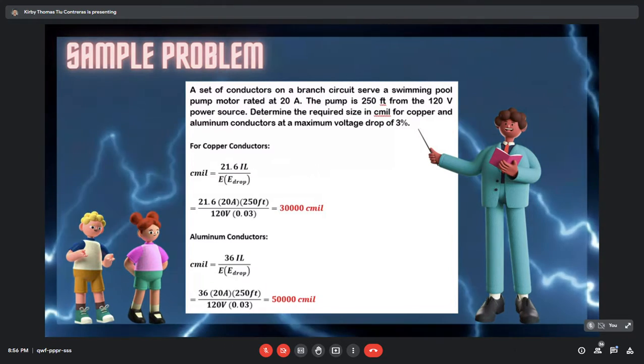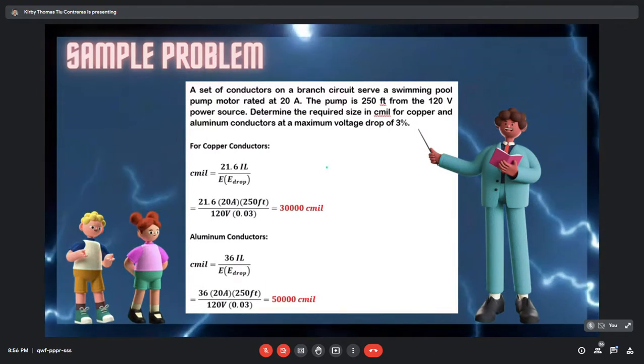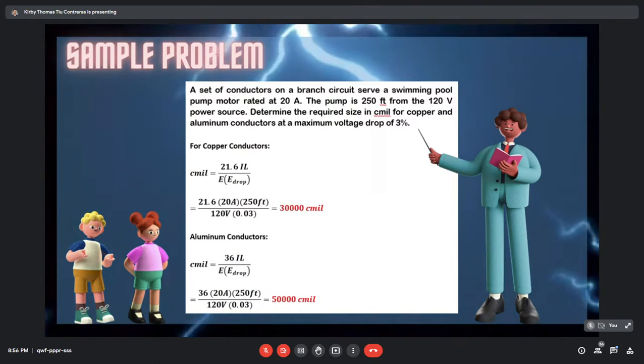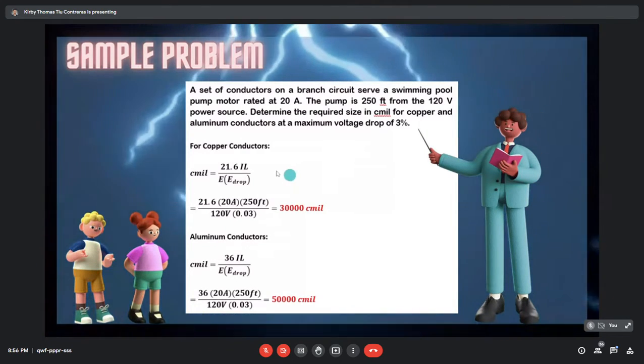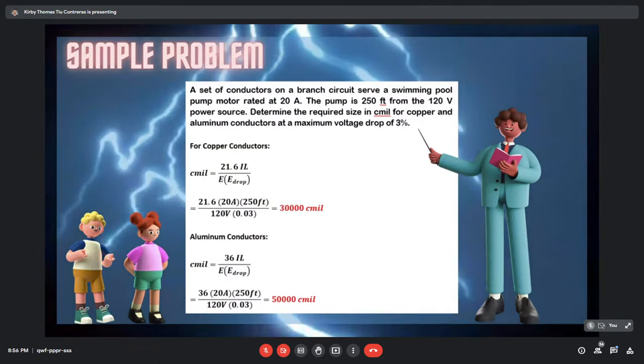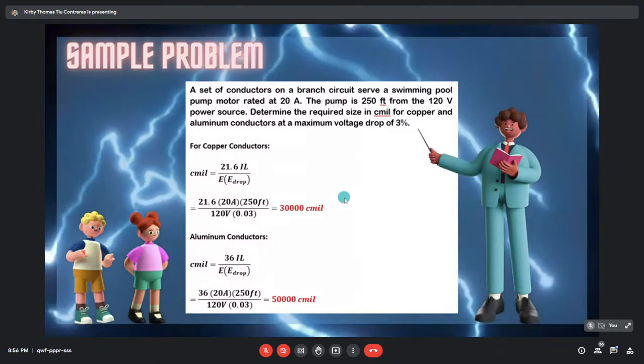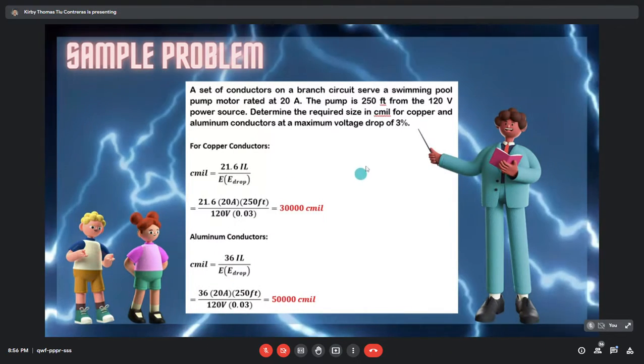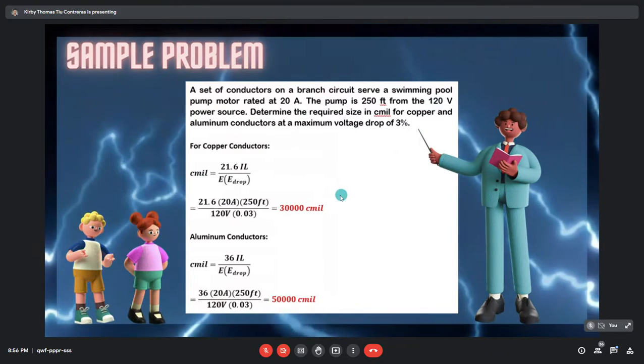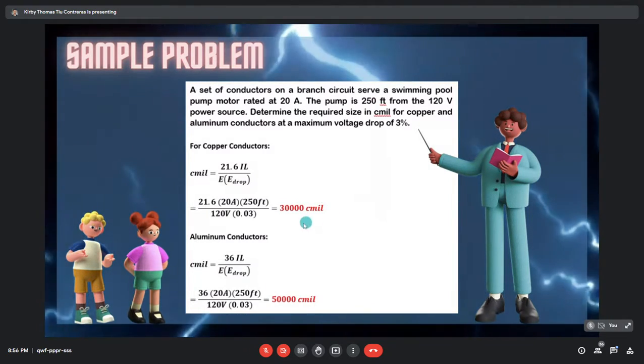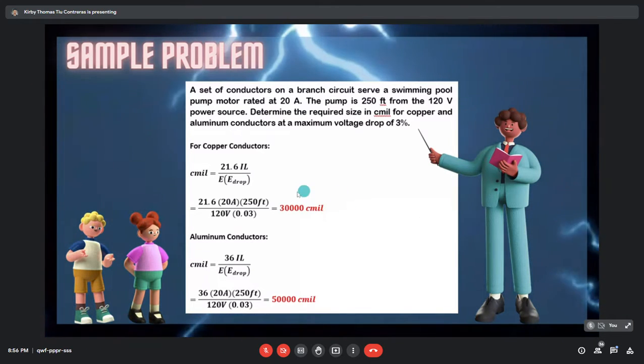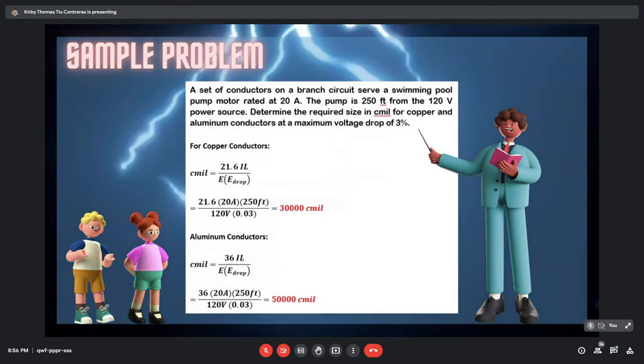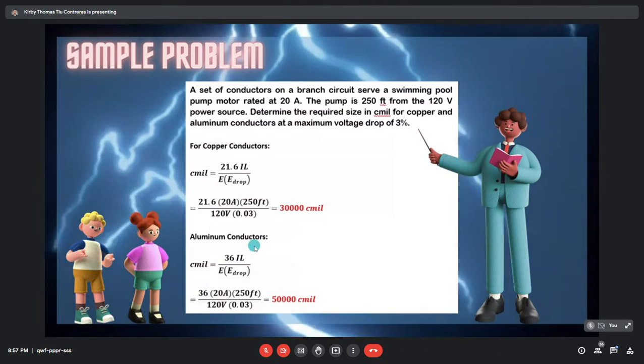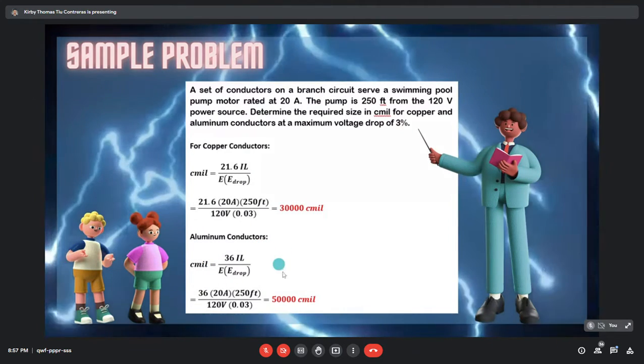So yeah, this formula is just a derivation from the original formula for determining the maximum length of the conductor. So the same process: direct substitution and then evaluate. So for copper conductors in the given condition, we'll get 30,000 circular mils, or we can convert it into KC mil by dividing 30,000 by 1,000. So 30 KC mil. For the aluminum conductors, same process, direct substitution, then evaluate.